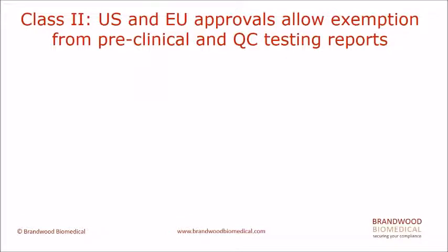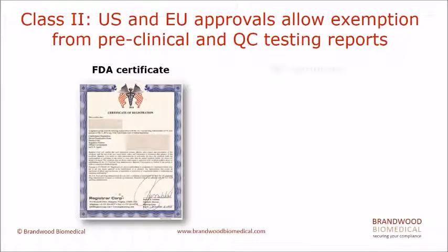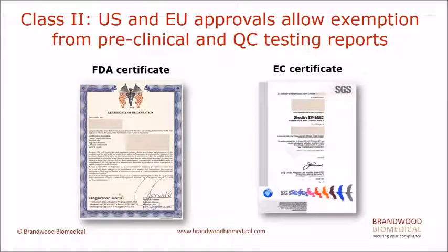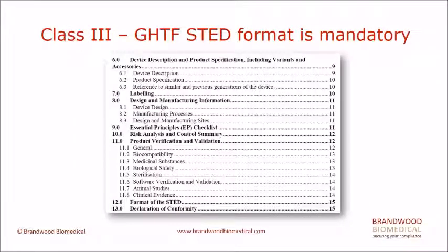So for Class 2 devices, if you have the US approval or the European approval, which is the EC certificate, the preclinical testing and QC testing reports can be exempted from the initial application. Please be careful: the product name, the manufacturer information, and the model number must be identical to the submission that's submitted to TFDA. For Class 3 submissions, the full GHTF technical file in the STED format is required.